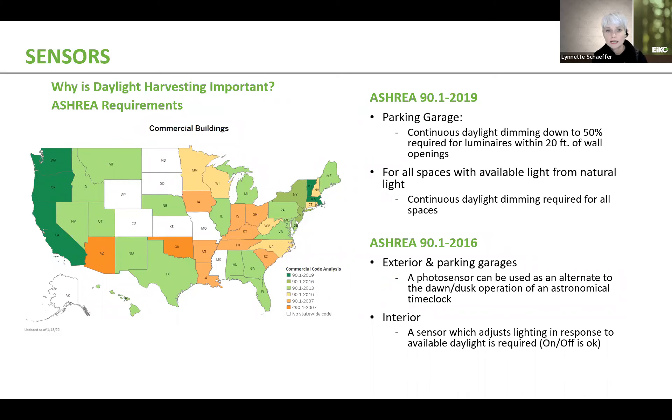Another big reason is it helps maintain and meet local codes and energy codes. So for instance, if you look at ASHRAE 90.1 2019, specifically for parking garages, it is required that continuous daylight dimming down to 50% is required for luminaires within 20 feet of wall openings. It also goes on to say that for spaces with available light from natural light, continuous daylight dimming is required for all spaces. Just depends on what ASHRAE code you are part of and what your local codes are. But daylight harvesting helps meet these different types of codes and requirements that now exist.